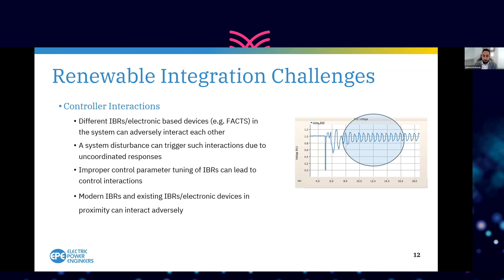Another point is recovery in weak grids. Canada is a large country. In many cases, some of the renewable facilities are connected in more remote areas, supplying power to the load centers. And so those parts of the system typically have weaker connections. Following a contingency event, the short circuit level at that point of interconnection may be significantly reduced because of the change in system topology. And in some cases, IBRs may not be able to stabilize after that fault clearance.